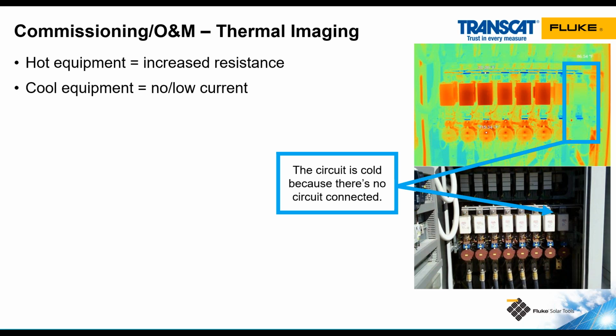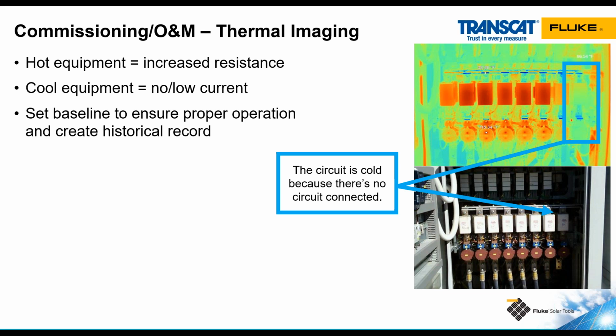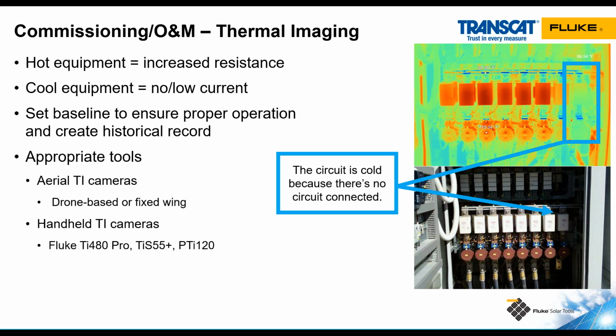If this was a combiner box and we saw a fuse holder that was cooler than the other fuse holders, we'd know that that circuit is not operating properly. There's probably an open connection somewhere in the circuit. At commissioning, we can use this thermal imaging data to set a baseline to see how things change in the future. I will say, when we're doing thermal imaging in solar, we're not usually looking for a specific temperature. We're looking for more qualitative data to see how things compare to each other.